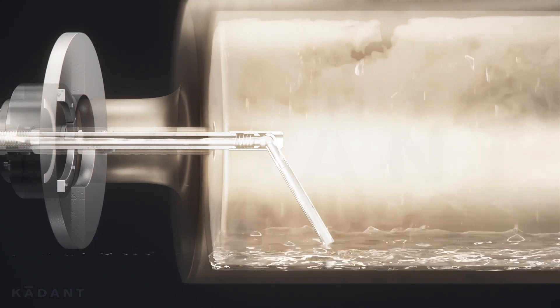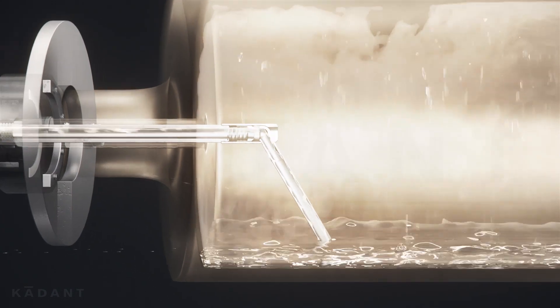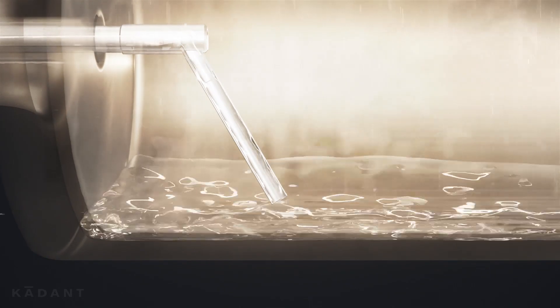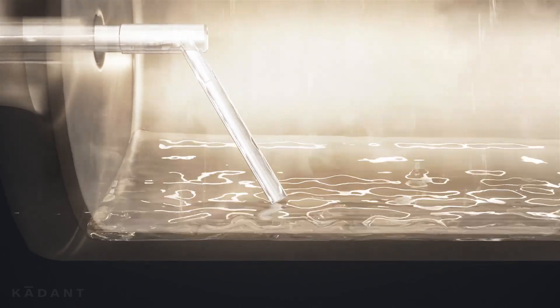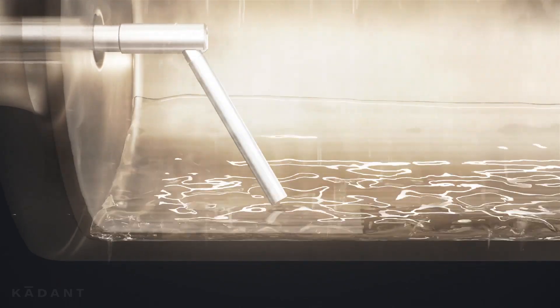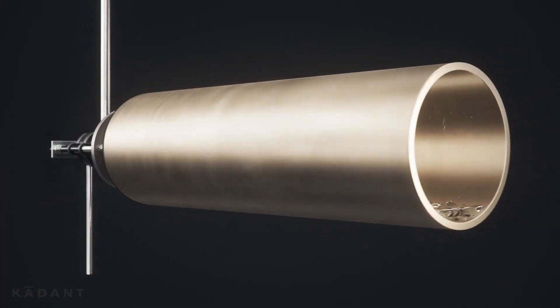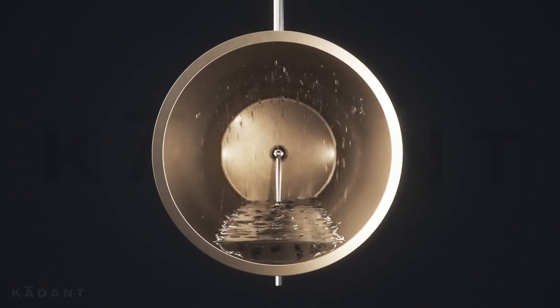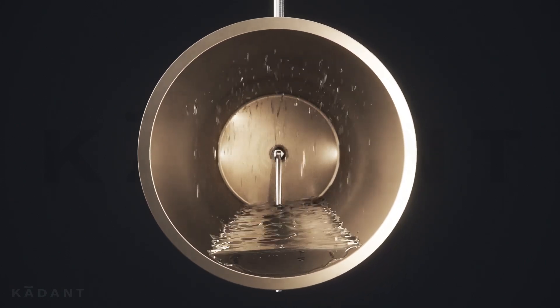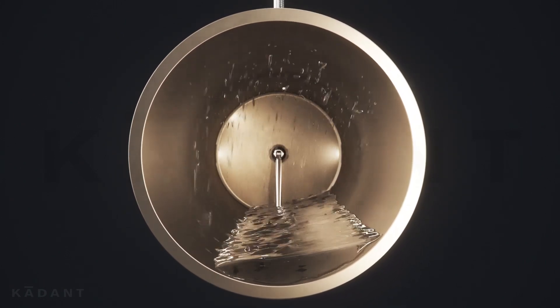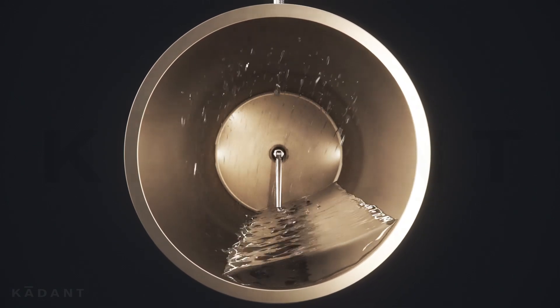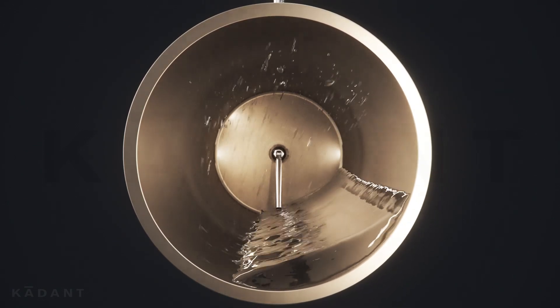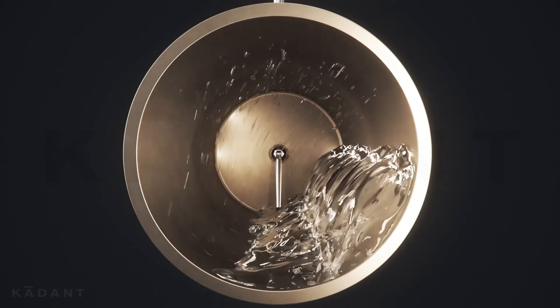Differential pressure pushes the condensate and some blow-through steam into the rigid siphon and back through the rotary joint. The blow-through steam and condensate are later separated and recycled in the steam system. The rigid stationary siphon is precisely positioned to maintain a layer of condensate that continuously cascades, creating turbulent movement and efficient heat transfer.